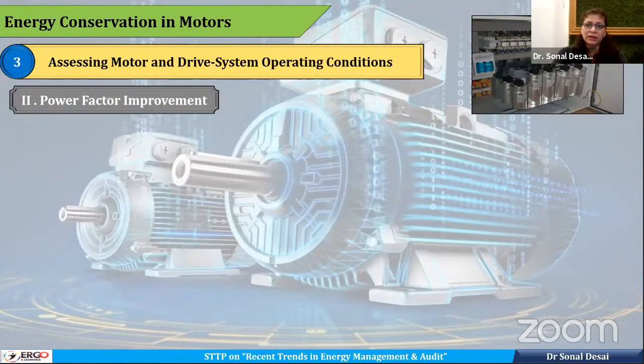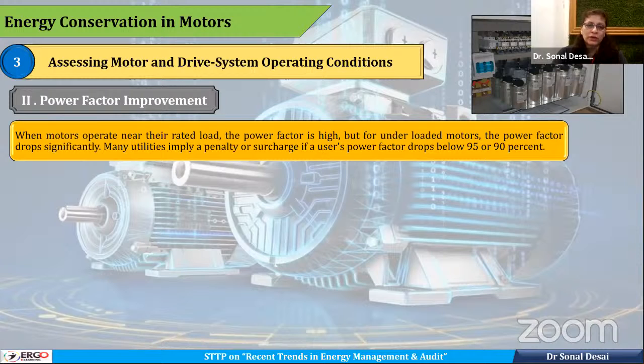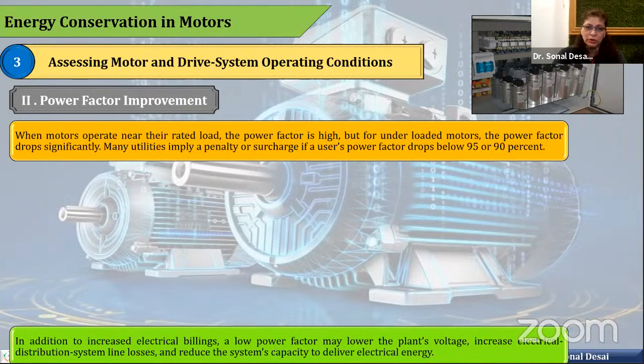Then comes another related topic with energy saving in motors, that is how to maintain the system operating condition, that is power quality and power factor. These two parameters are also important when we talk of motors. When the power factor drops below 95, some companies levy a charge. In some utilities, it is below 90 also.